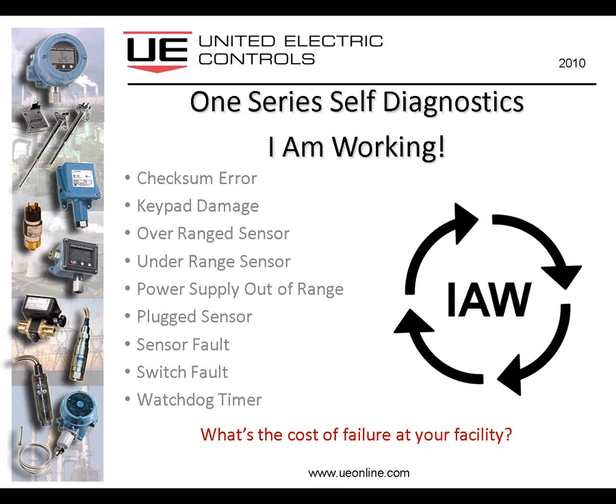You might consider switches that are mounted outside, and perhaps last night we had a lightning storm, and perhaps the lightning struck the instrument. Well, you know, it's going to do its best to continue working. However, it has detected that part of the software was damaged by the lightning strike. Although it appears to be working, there's a checksum error, and the 1 Series will alert us to that fact.